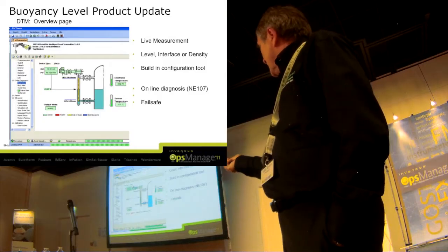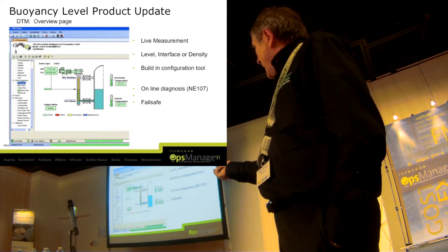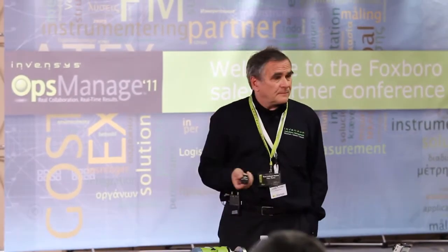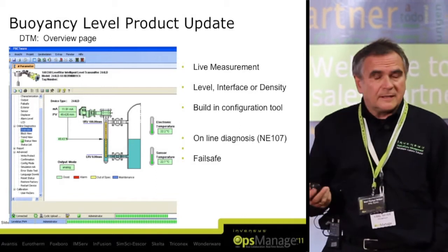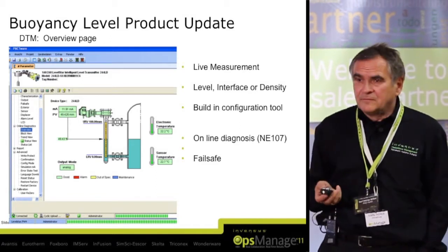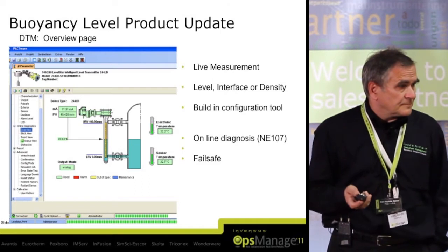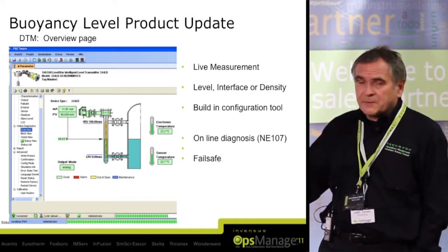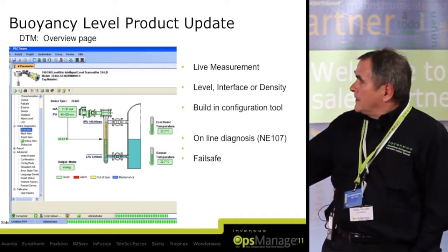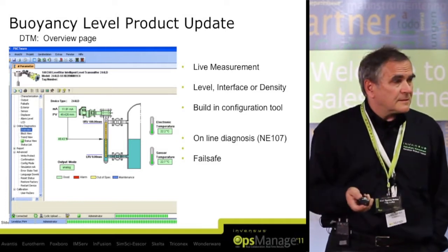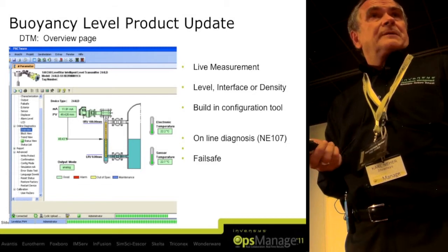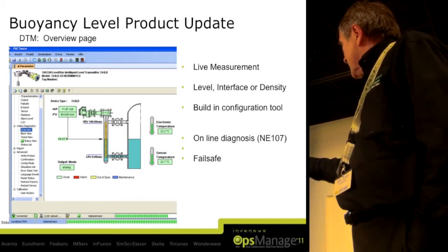In a normal application, you have a tank or reactor and a bypass, so you have a displacer chamber as a bypass. Always you need a displacer element, and on this displacer element there is a buoyancy force from the liquid and the liquid level. So displacer element and transmitter are always used together. The displacer chamber as a bypass is used in 80% of applications. Of course, you can also mount this transmitter on top of the tank, but for this kind of application it is not so common.